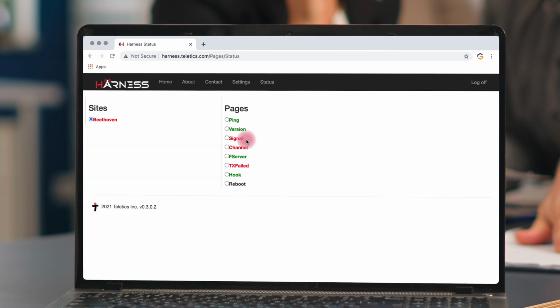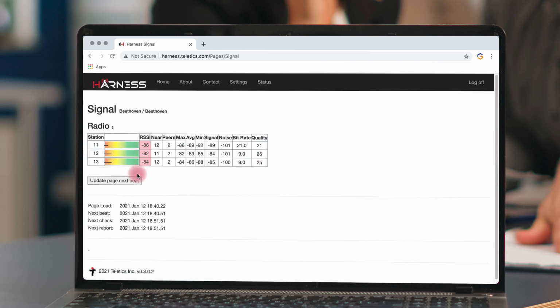In the signal level, you can actually see what's going on with the radio signal level health. In this case, on the demo system, what we've done is we've put what are called test loads on the outputs of the radios. So they're artificially low even though the radios are very close together. So a technician that looks at this can say, okay, I've got an issue with these particular signal levels. Either I've got a bad antenna, or maybe the customer has put something in the way of the antennas between the radios. And then sometimes you can save yourself a field visit by knowing that.